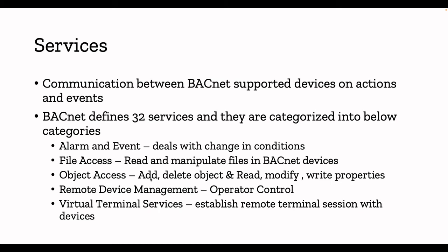Third is object access — as we saw, we can add, delete, read, modify, and write the properties of objects. Fourth is remote device management, mainly for operator control. All BACnet devices will be connected, and there will be a separate operations room where people sit and monitor what is happening with the entire building. Fifth is virtual terminal services — to establish a remote terminal session with your devices, just like SSH. Within a BACnet network you can reach a device and check as per your need.